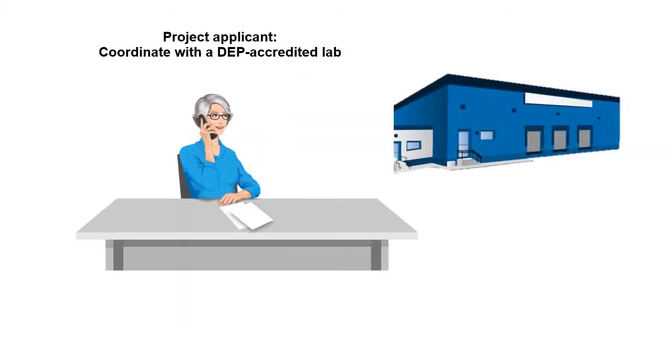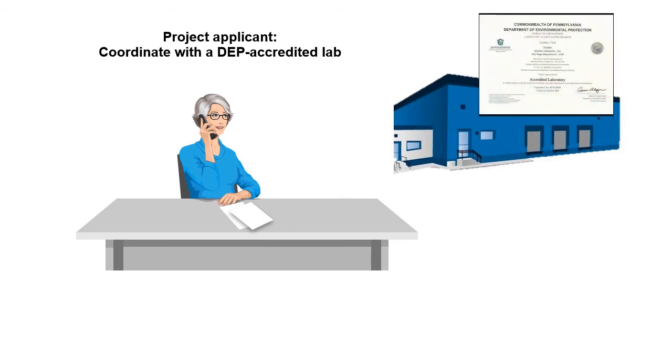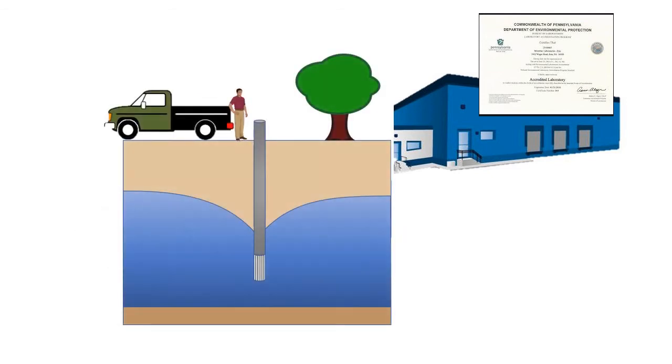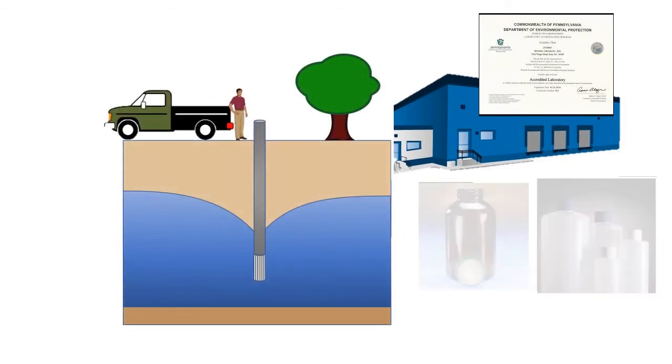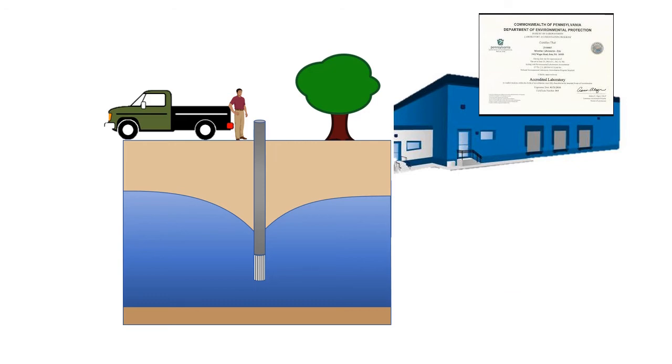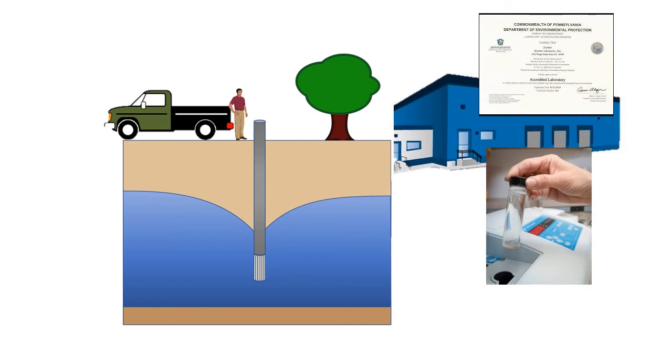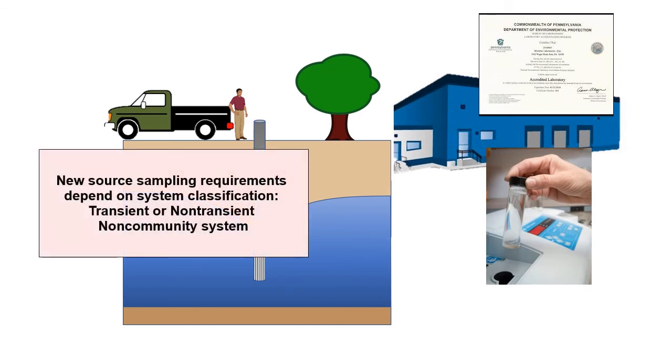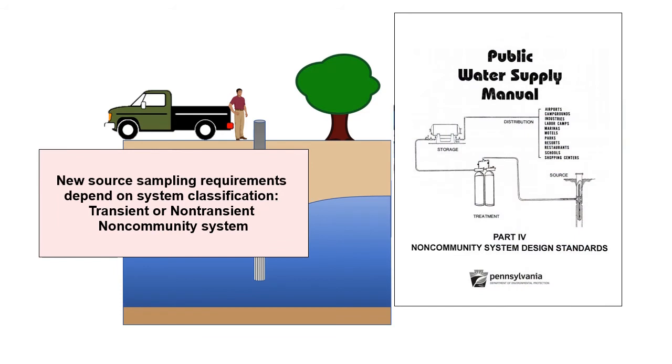It is important to note that prior to the pumping test, the project applicant must coordinate with a DEP accredited lab regarding water quality samples that are collected toward the end of the pumping test. Samples should be collected in laboratory issued bottleware and they are typically collected by the well driller, the laboratory, or the project applicant. The project applicant must make sure that the laboratory analyzes the samples for the correct parameters, which depends on if your system is classified as a transient or a non-transient system. Details on the applicable new source sampling requirements are provided in the Public Water Supply Manual, Part 4, Non-Community System Design Standards.